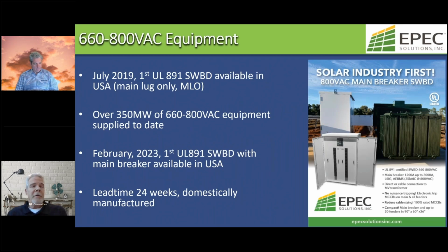A lot of the time we spend really educating customers, because when it comes to over 600 volt equipment, it's not as easily accessible as the typical 480 volt equipment is. However, early on, we jumped out with UL after we made our basic 480 and 600 volt switchboards. We also moved forward in July 2019, and we got our first UL891 switchboard rated up to 800 volt approved and short circuit tested. At the time, the equipment that was available was actually only feeder breakers, so it was a main lug only switchboard. Since that time, we've been supplying main lug only switchboards, and over 350 megawatts of equipment are now running successfully.